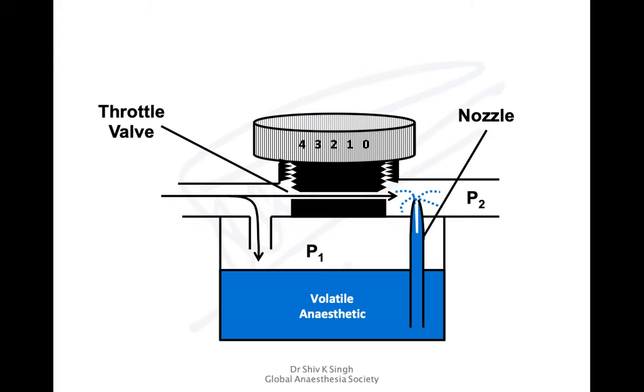There are some vaporizers which have an injection system. The reason why I'm mentioning it is because of the Tec vaporizer. Some people wrongly call it an injection system. It's not an injection system, because we will discuss the Tec vaporizer in a lot more detail. And so this is an injector vaporizer, wherein the anesthetic agent is injected into the bypass chamber.